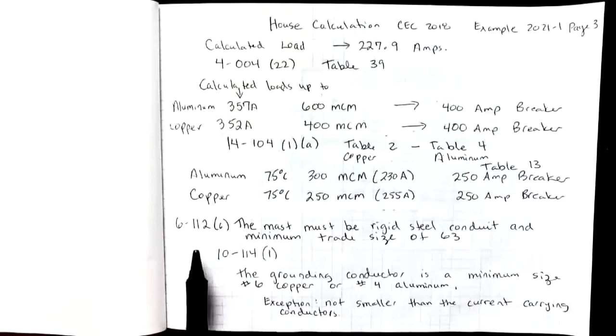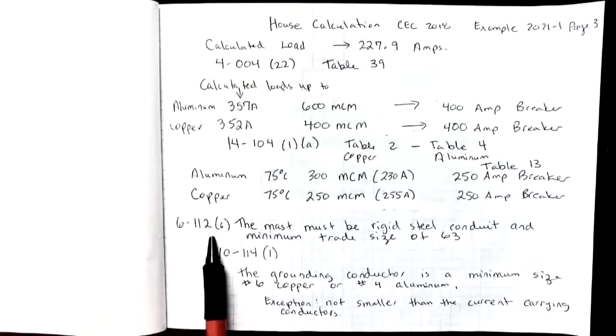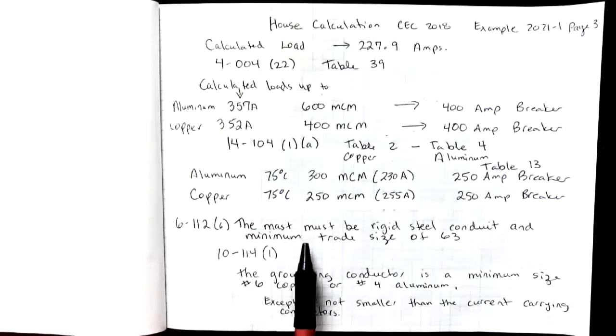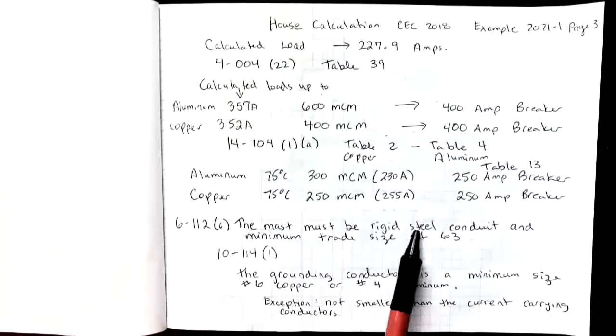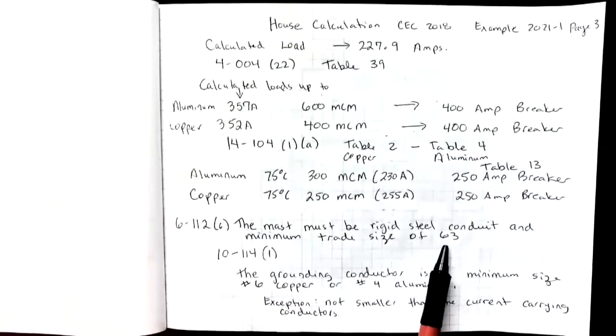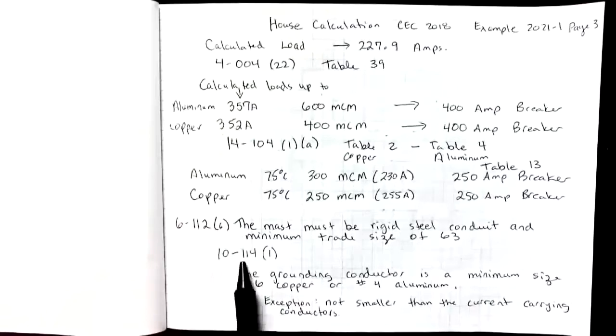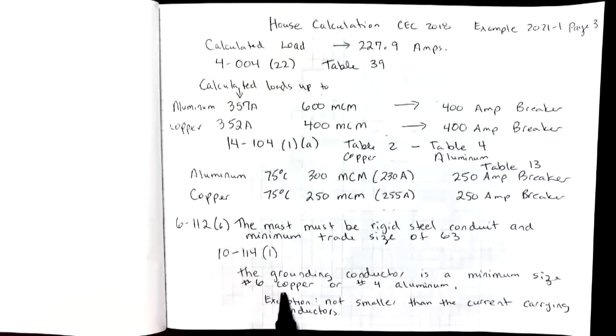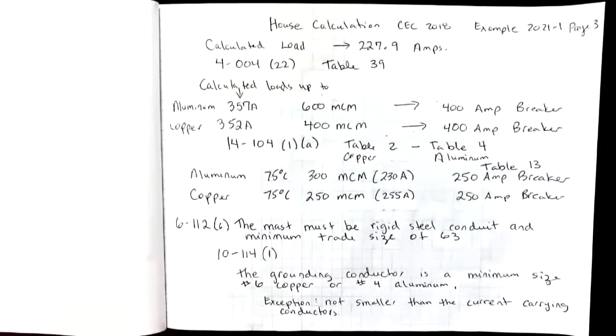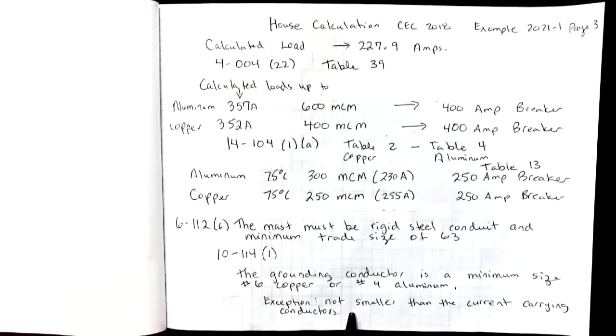Once we decide on wire size, we can then look at rule 6-112(6). It says that if we're going through the roof and we're going to use a mast, the mast must be rigid steel and minimum trade size of 63. Then rule 10-114(1) tells us that the grounding conductor needs to be a minimum size of number 6 copper or number 4 aluminum. And there is an exception. We could go smaller for that ground size as long as the ground wire is not smaller than the current carrying conductors. In this case, our current carrying conductors are much larger, so we better go with the minimum size of number 6 or number 4.